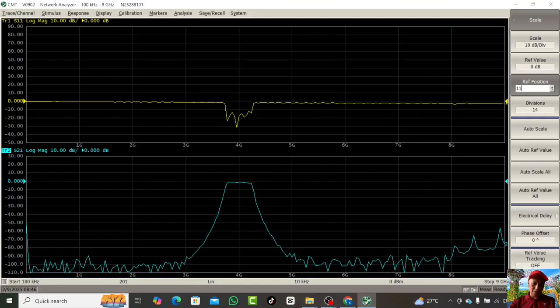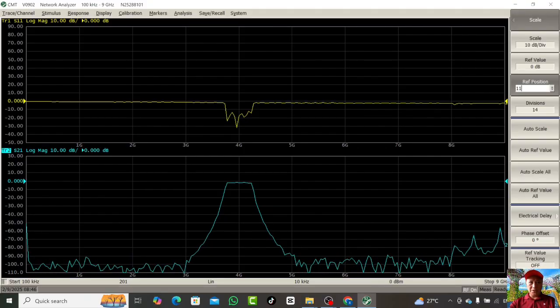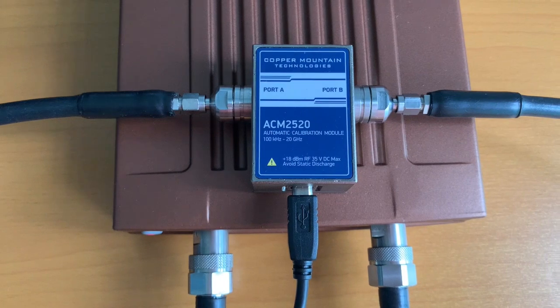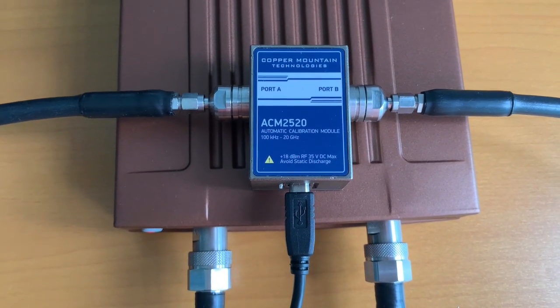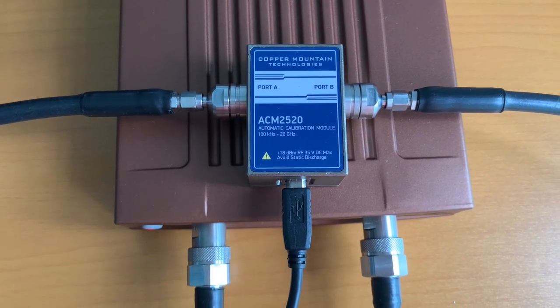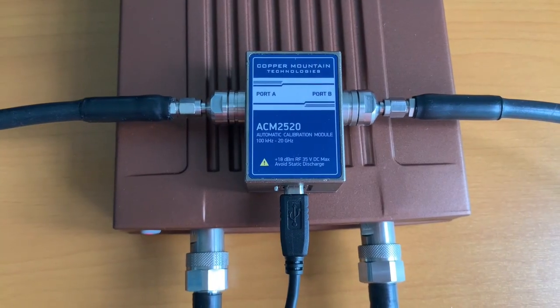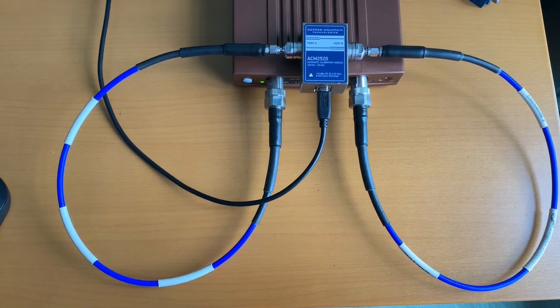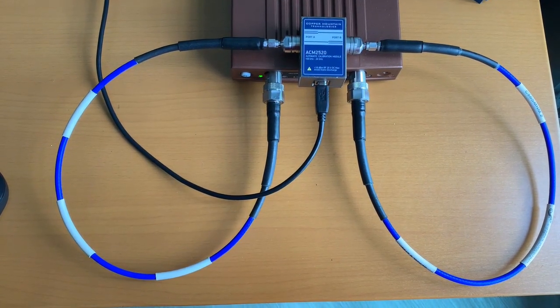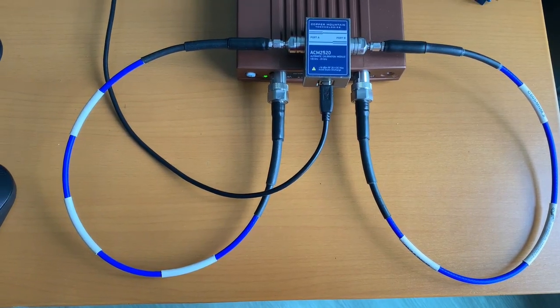But this is not accurate because we haven't done the calibration yet. But let's say the operation frequency of the filter is around 3 gigahertz to 5 gigahertz. That should be enough. So okay, then I will remove the filter and do the calibration. The start frequency is 3 gigahertz and the stop frequency is 5 gigahertz. And this ACM2520 is the auto calibration module from Copper Mountain Technologies. Now I connect the ACM to the VNA and conduct the calibration from 3 gigahertz to 5 gigahertz.